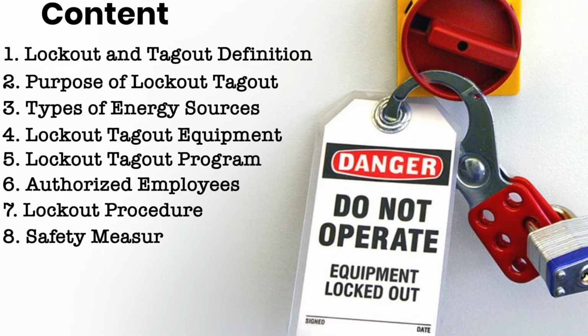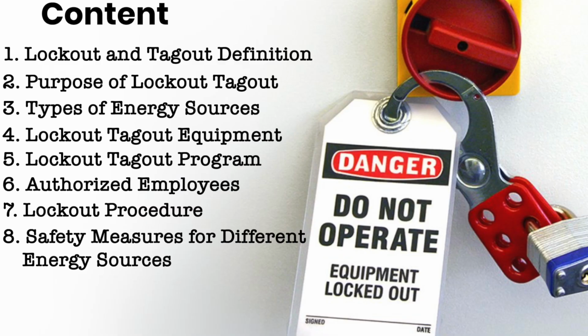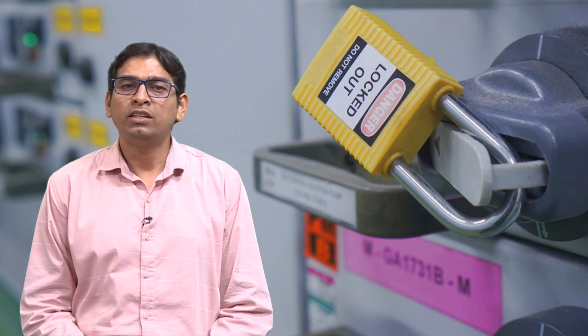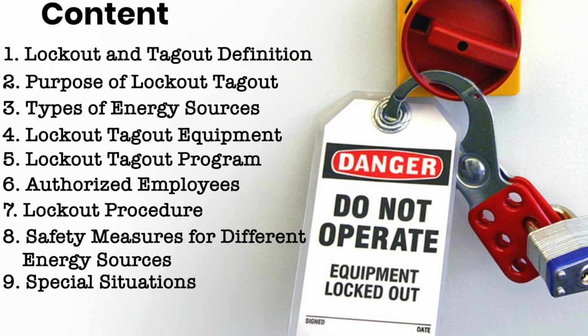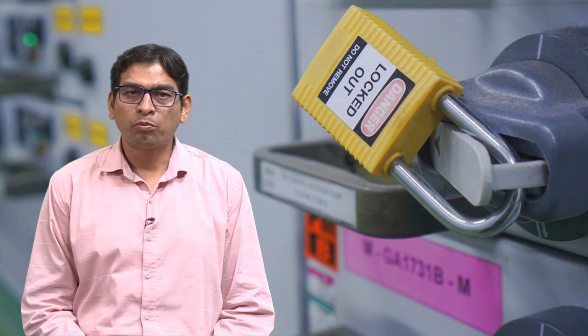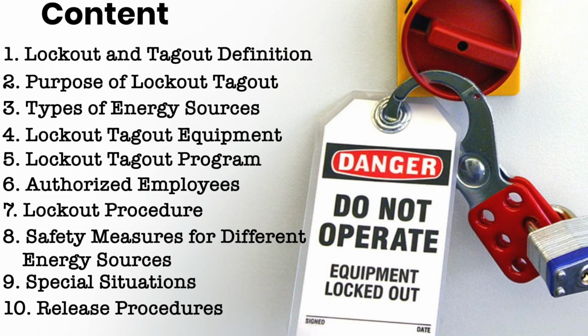The steps of a proper lockout procedure include notifying necessary personnel, attaching lock devices to energy sources, and testing the equipment to ensure it will not operate. Eighth point, we will see safety measures for different energy sources like electrical, hydraulic, and pneumatic systems. In the ninth point, we will see special situations in which lockout and tagout is necessary: arc flashes, personnel changes during servicing, multiple pieces of equipment powered by the same energy source. Tenth point, we will see the release procedure, how we can release the lockout and tagout.